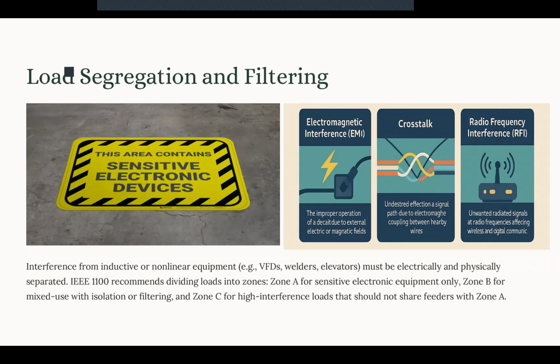We have zone C, which is the high interference loads. So there are loads that generate significant electrical noise or transient or harmonic distortion. It could be motors or welders or elevators or compressors, those kinds of loads are considered zone C. There are some design requirements.